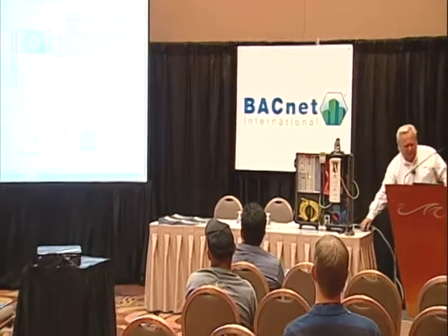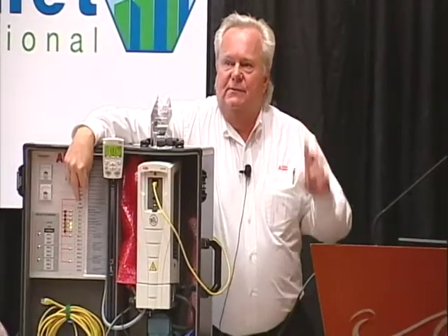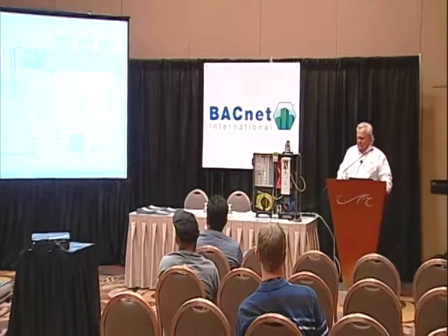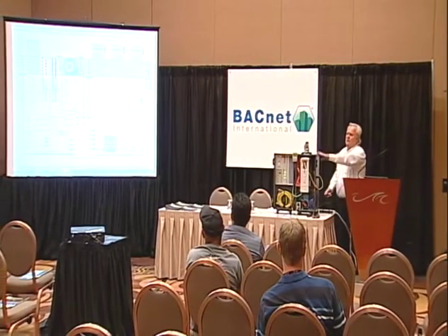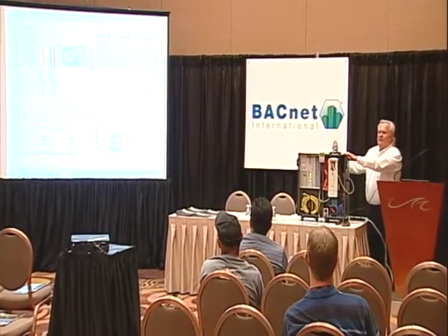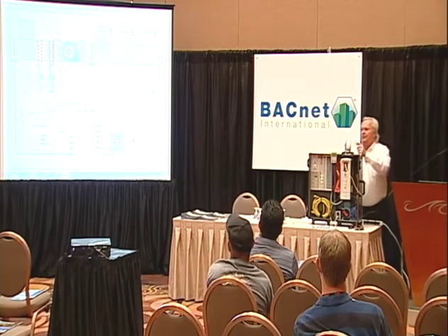So, in real world operation, 6 o'clock in the morning, time for building cool down. Building automation system says start. When it does, first thing you'll see is two of the lights from the relays firing, and you'll hear them. You'll hear your relays close, and you'll see on the graphic the dampers start opening. If everything's working right, yeah. So the dampers are opening. Now when they get all the way open, the end switch comes back to the VFD. And because my set point's 1.5 inches, my feedback's 1.2 inches, it's going to speed up this fan because I got less pressure than I need in a duct.